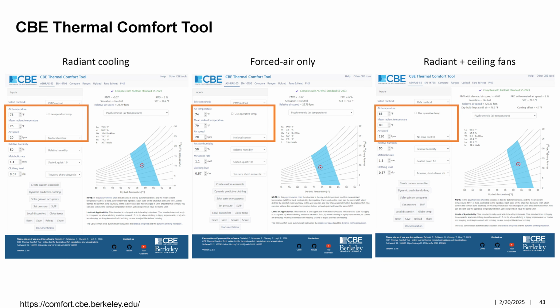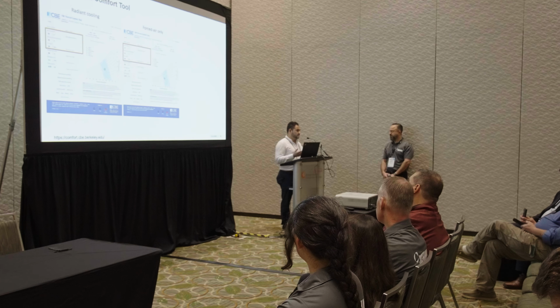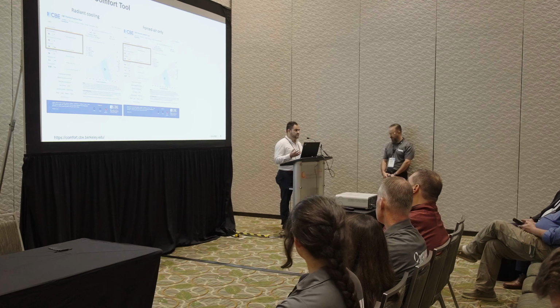In this example, I showed the operating conditions of a radiant cooling system, and as you can see, these conditions comply with ASHRAE's thermal comfort standards. We can visually see this with the red dot being in the blue thermal comfort zone. We can also do the same thing with forced air systems, and as Saeed explained early on in the presentation, we can use various combinations of air and mean radiant temperatures to create a thermally comfortable environment, but that has implications on how we're going to design our HVAC system to actually achieve these operating conditions in the space.